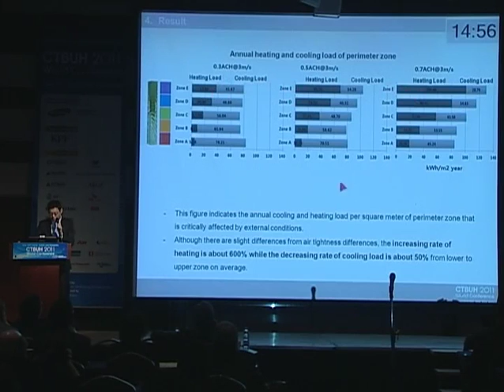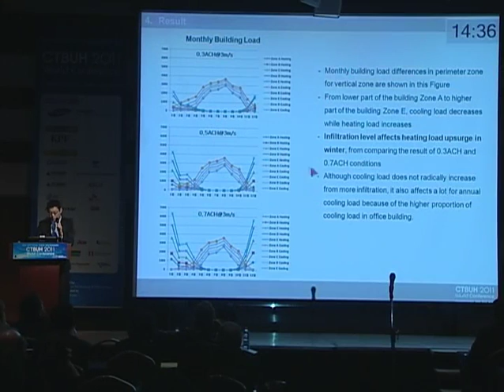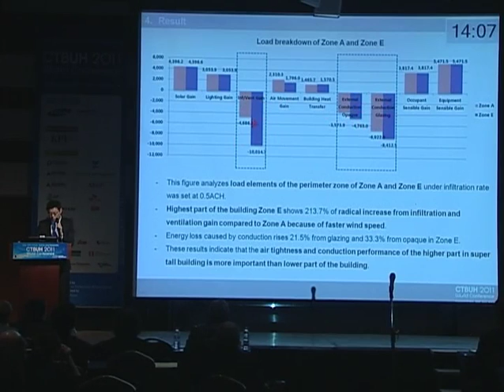And this is a monthly building load. You can see the bigger difference, especially in the winter season, because it's getting colder outside and the wind speed grows. And although it seems there's not much difference in cooling load, in the annual sum it is quite a big value. And this is a load breakdown from zone A and zone E, which is the lowest and highest level. And you can see there's no big difference in solar load, because the effect from the other buildings is not considered. The simulation just assumed there's no building nearby. So infiltration and ventilation gain and the conduction from the building envelope show big differences.